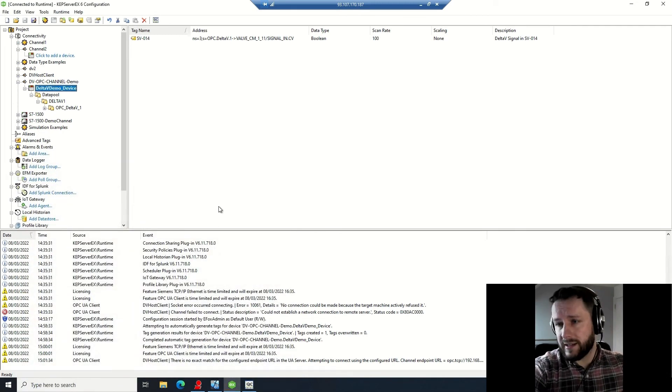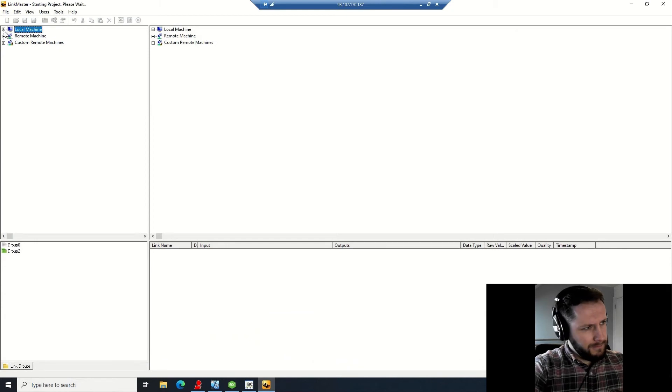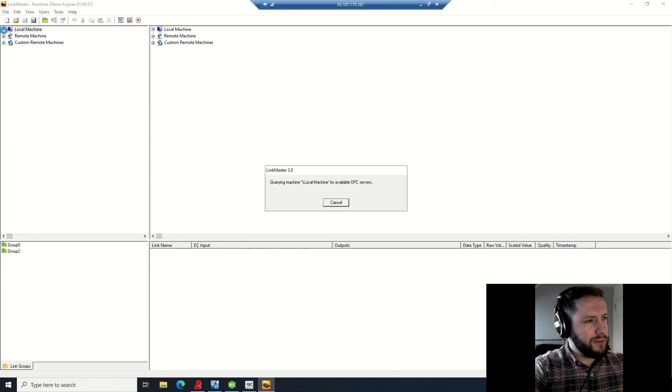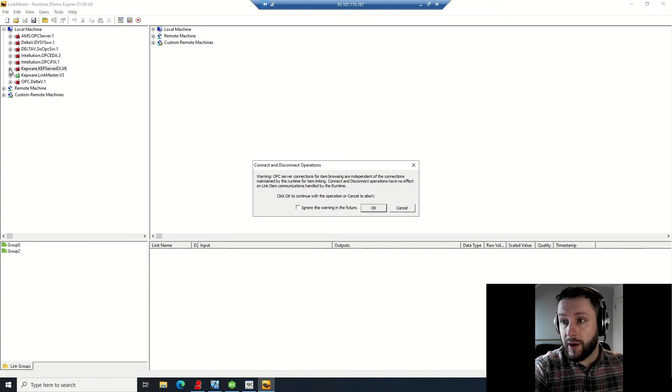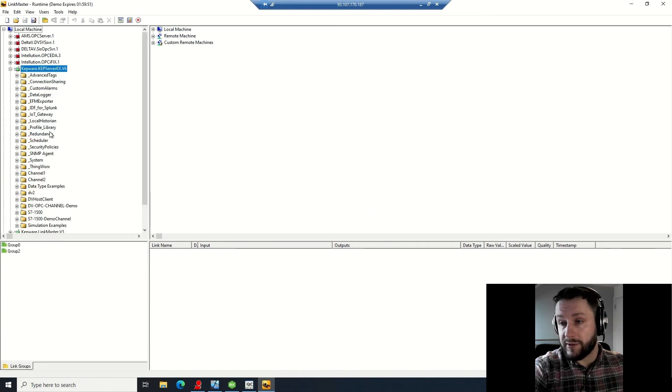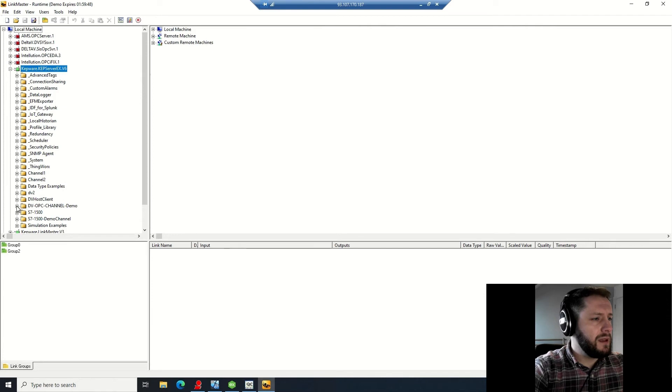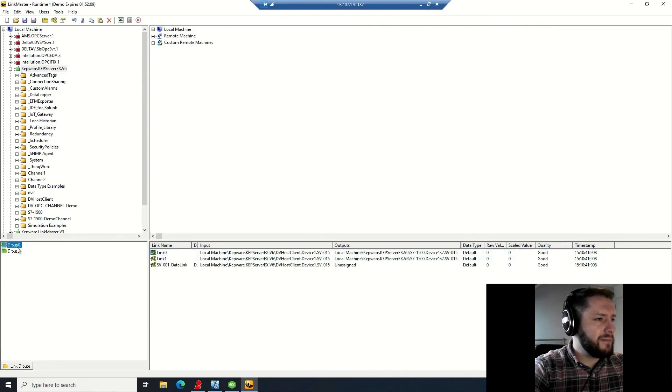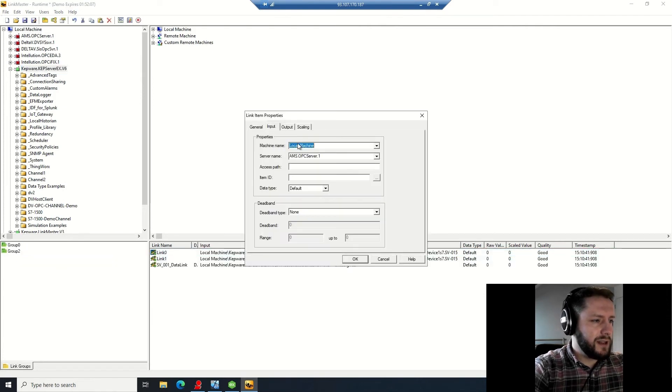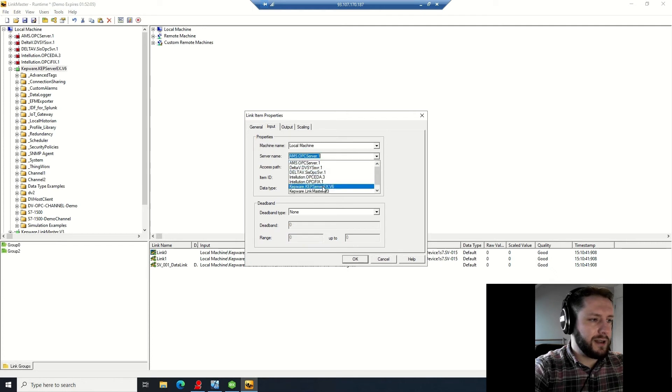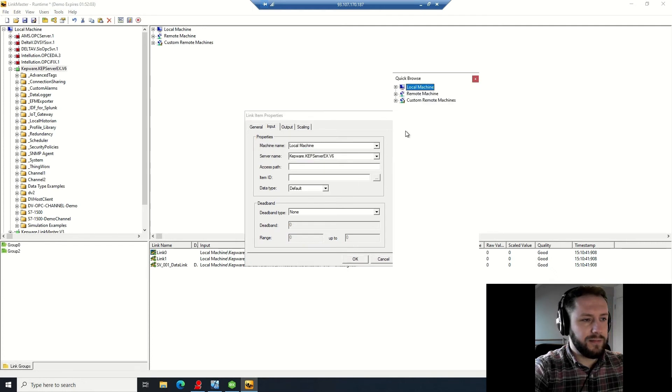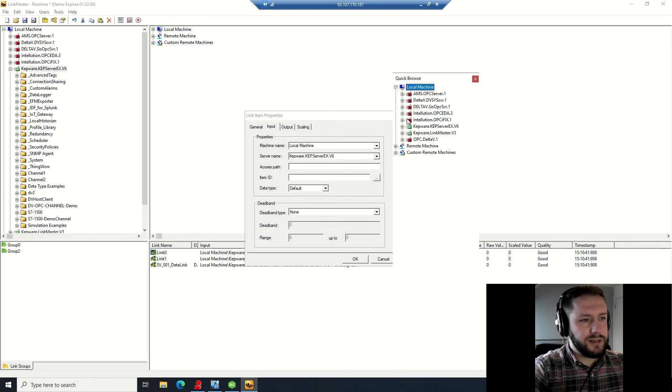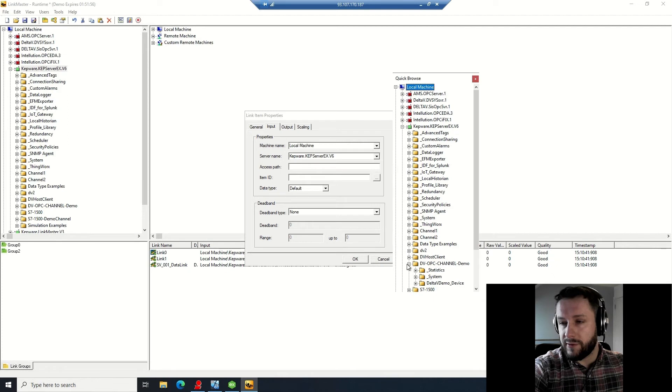So now I'm going to link these two tags together by using Link Master. You want to open it up, open up your local machine or where your Kepware server is. In this case it's on the local machine. You want to browse down to Kepware KEPServer - that's the name of the server. You want to come down here to the bottom left hand panel, right click, click create group, then create link. And then you're going to want to browse an input to the Delta V signal which you've created on Kepware.